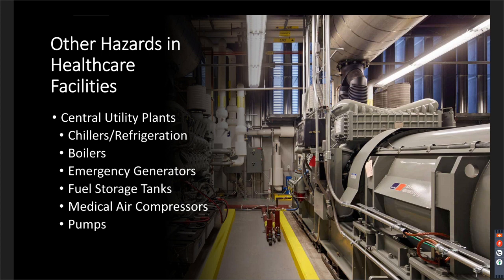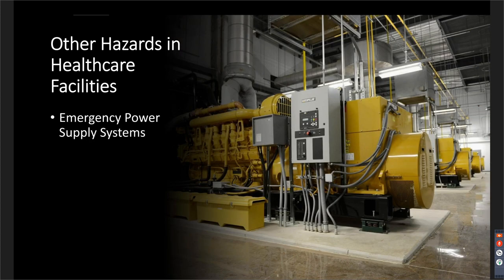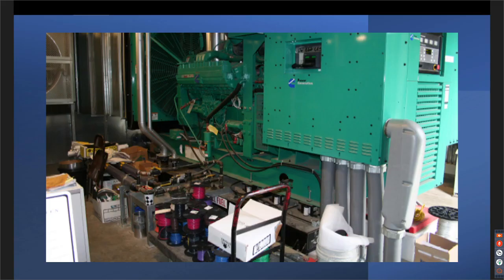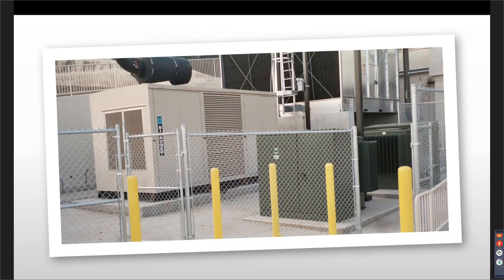What about central plants? Are there hazards in central plants that you might come across? Refrigeration, boilers, emergency generators, fuel storage tanks that go with emergency generators, medical air compressors, pumps, etc. A lot of requirements for emergency power supply systems. We went over many of the requirements in session 1 on Tuesday. The requirements for the generator include operational considerations, so storage right up against the day tank or right up against the emergency generator could be a problem. Might want to find somewhere else for that.